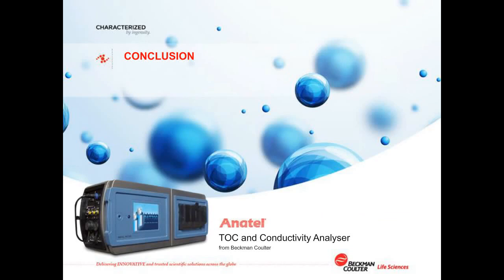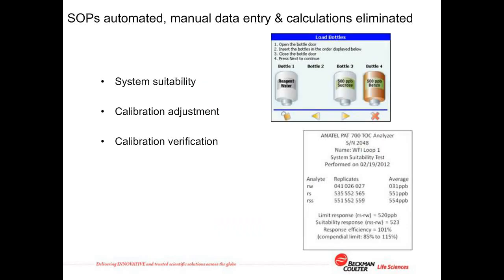So we've learned that TOC and conductivity analyzers can be strong allies to help us keep our water systems under control. We've learned how calibration is important and how complete oxidation is recommended in the European Pharmacopoeia for complete and accurate TOC analysis. So let's take a look now at how the PAT700 TOC and conductivity analyzer can help support you through the challenges of moving to water for injection production, moving from using reverse osmosis.